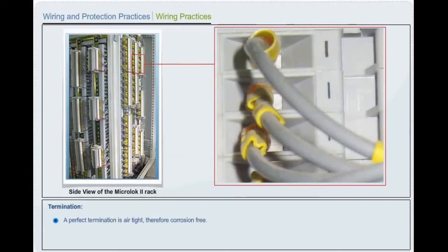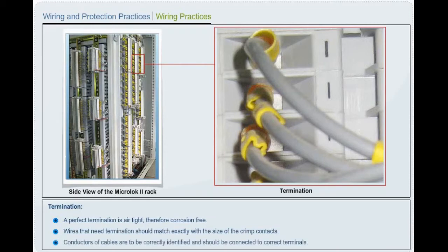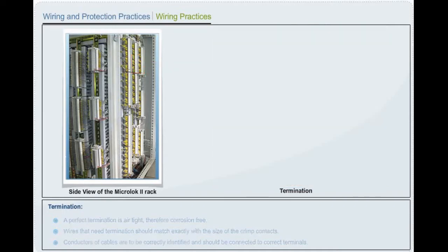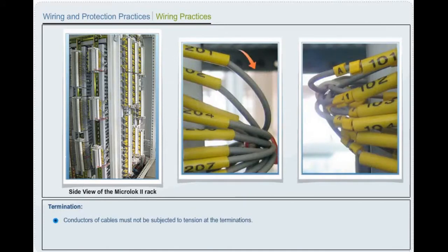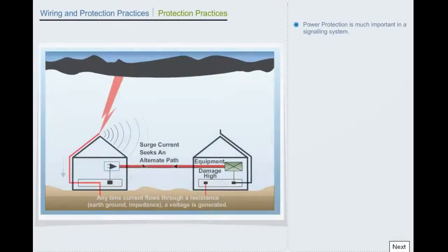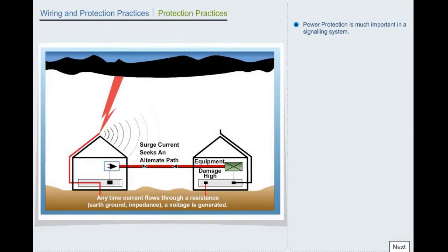Termination. A perfect termination is airtight, therefore corrosion-free. Wires that need termination should match exactly with the size of the crimp contacts. Conductors of cables are to be correctly identified and should be connected to correct terminals. Conductors of cables must not be subjected to tension at the terminations. Wiring and protection practices. Protection practices.